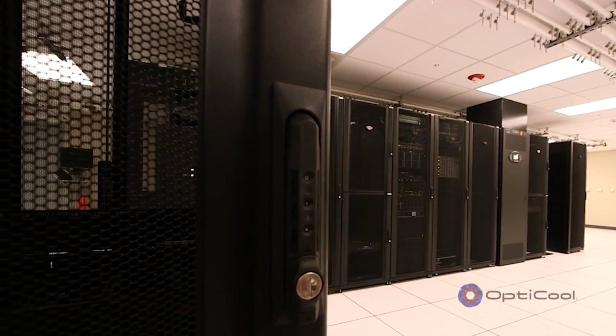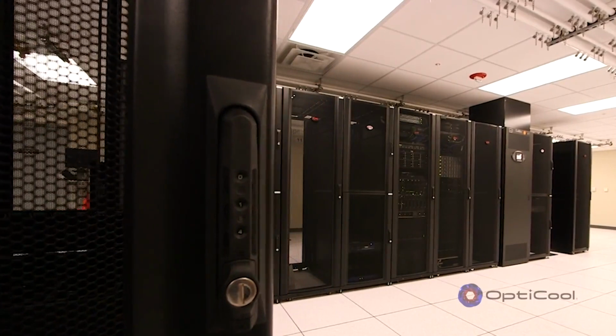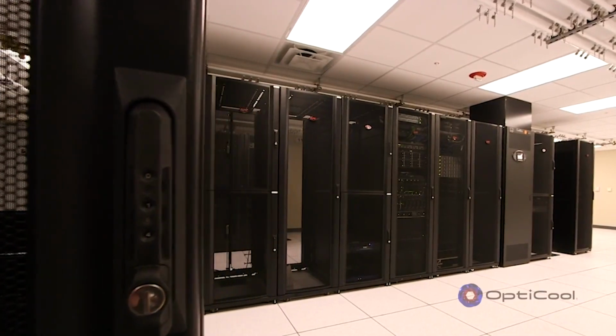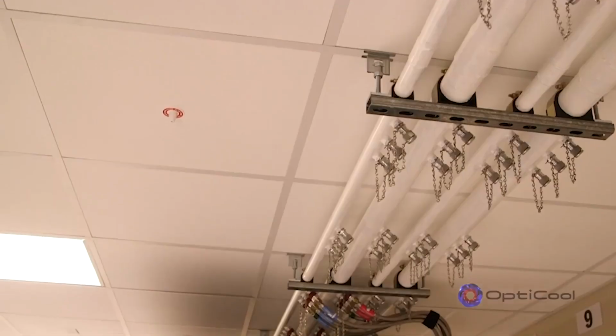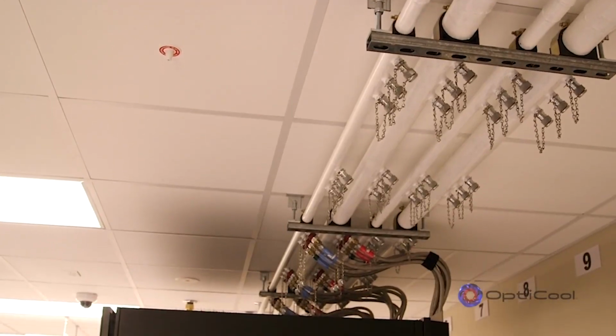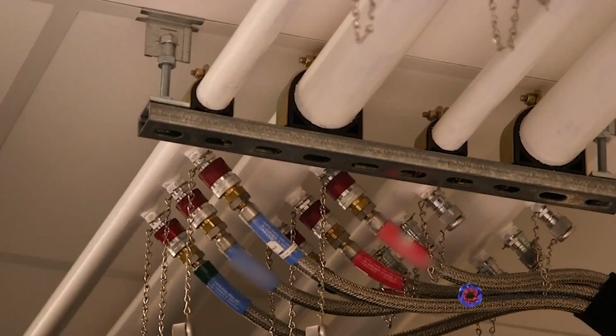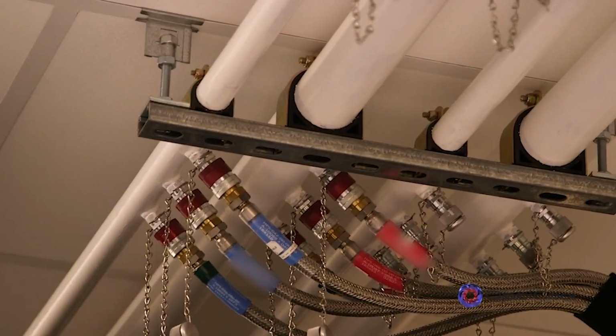We have a data center starting from scratch, and we're filling it with cabinets as we go. At the beginning, we were able to cool one cabinet. We're not running a 30-ton CRAC unit with all these compressors running. As we go, we just add a cabinet and plug it into the OptiCool and it takes over. It's scaling along, as opposed to a conventional way where we're cooling the whole space.